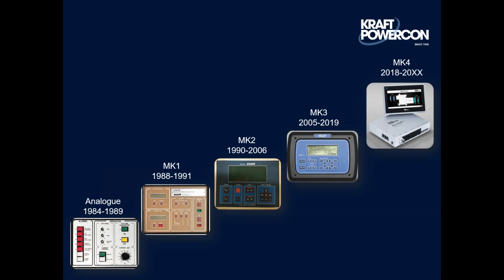We're available for a phone call when they have those questions, but it's basically plug and play. You pull out the old controller, put the new controller in, plug it in. All the configuration and settings are done at the factory. That's something we pride ourselves on at Kraft Powercon. You're buying a system from us, you're buying a solution. Why go through all the configuration, settings, and commissioning again? Even the spare part controller has all the configuration, settings, and calibrations done at the factory. There's nothing you need to do but hit the on button.